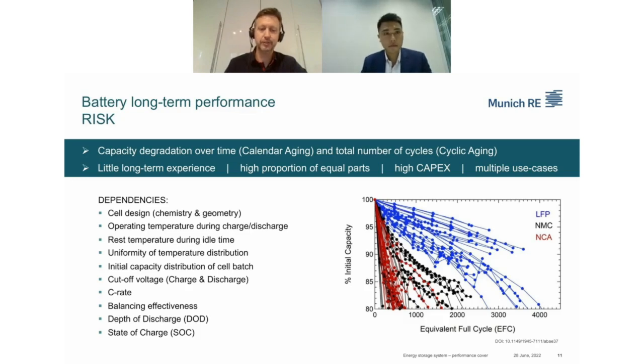The figure on the right shows the capacity degradation over the number of battery cell cycles for the three main cell chemistries: lithium iron phosphate (LFP), nickel manganese cobalt (NMC), and nickel cobalt aluminium (NCA), under different boundary conditions. In particular, C-rate, DoD, rest SOC (state of charge), temperatures, and cutoff voltages during discharging and charging have a significant impact on the end-of-life equivalent full cycle number, which is a crucial value for the achievable asset revenue.